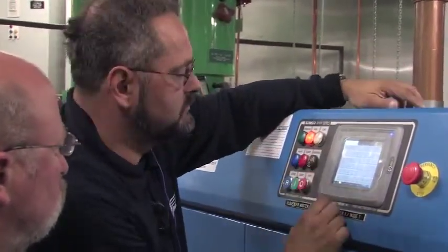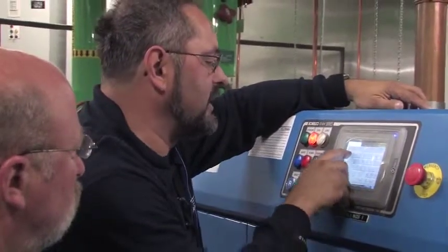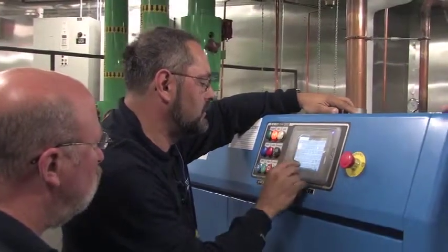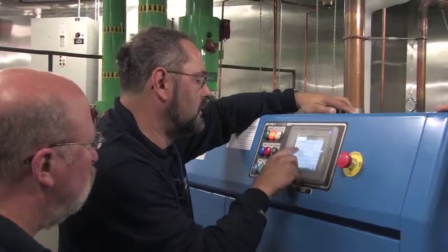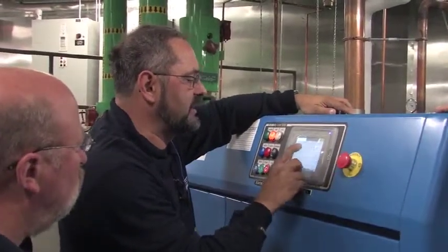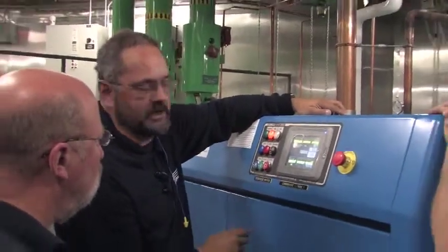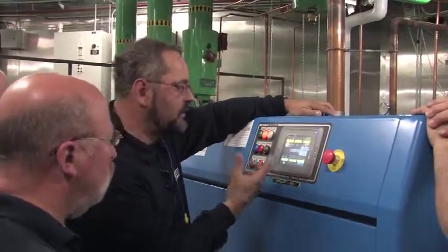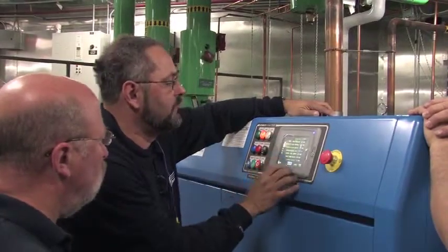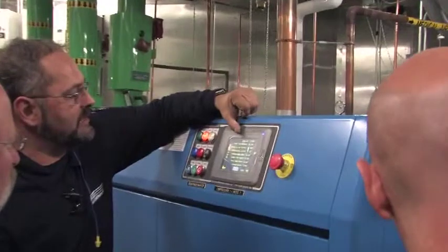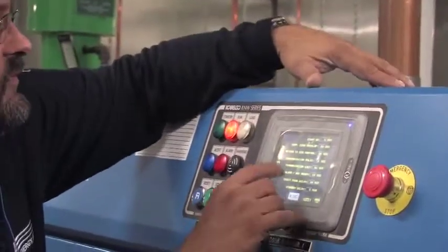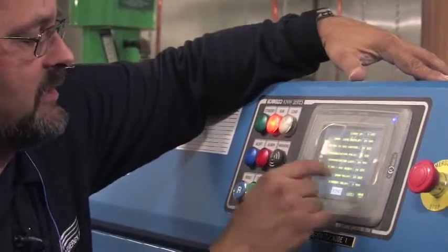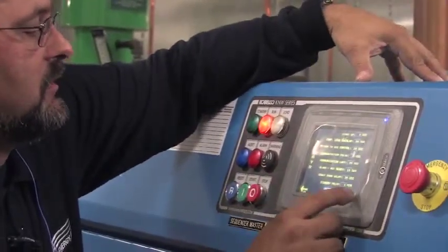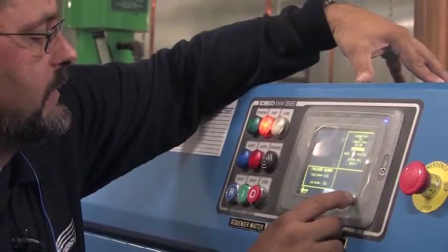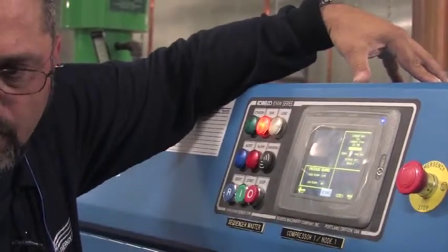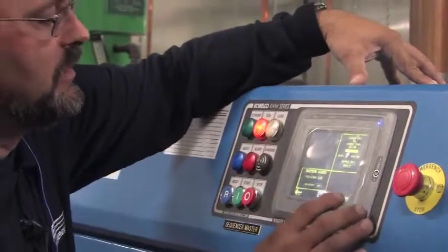Now the settings. That's the one thing I don't like. If you put this level password in on the first level, the unit run screens, if you put the configuration password, it lets you into all of them. All right. So, startup delays, lead overlap to allow the sequences to shift. How long, you know, you shut down, the alarms go off for various things. There's a whole section in that manual about the program that goes through what all these things are and what they mean.